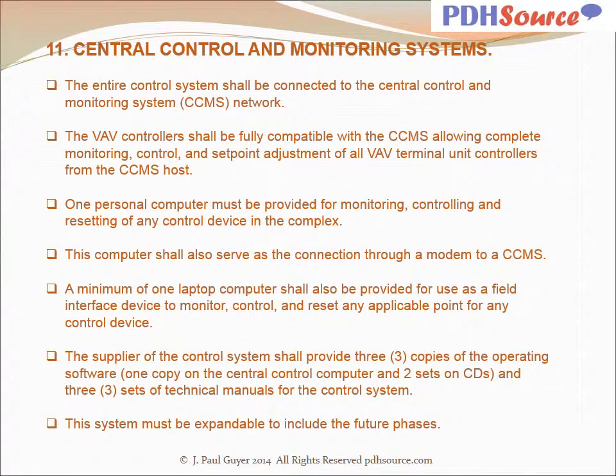The entire control system shall be connected to the Central Control and Monitoring System, CCMS, network. The VAV controllers shall be fully compatible with the CCMS, allowing complete monitoring, control, and set point adjustment of all VAV terminal unit controllers from the CCMS host. One personal computer must be provided for monitoring, controlling, and resetting of any control device in the complex. This computer shall also serve as the connection through a modem to a CCMS.